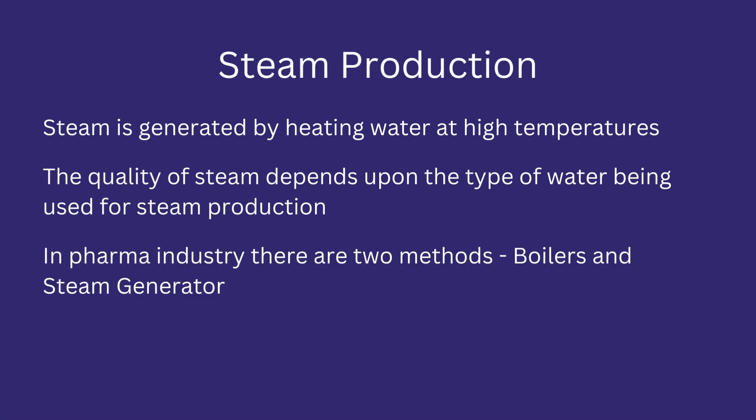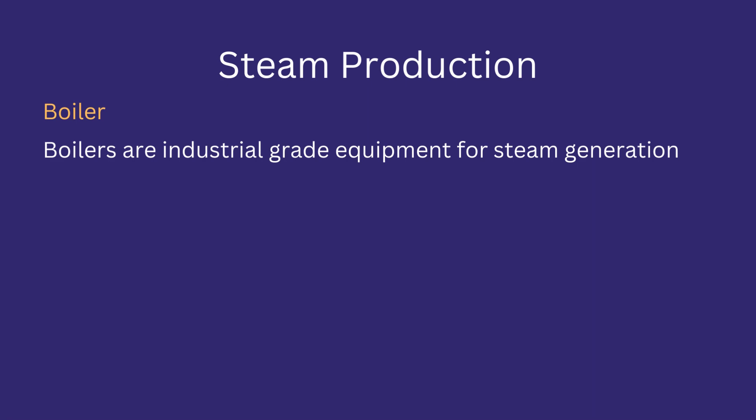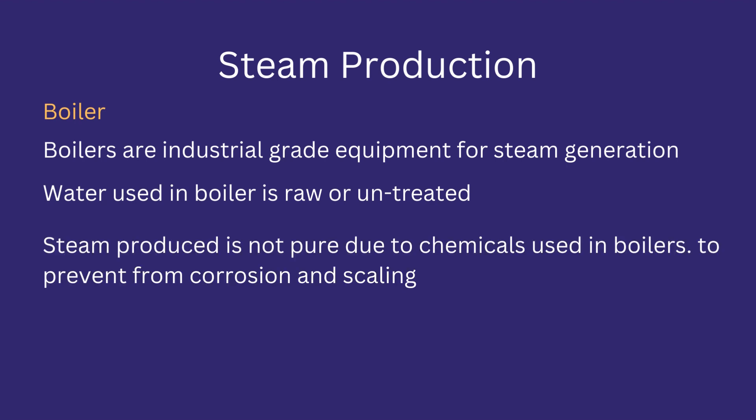In the pharma industry, there are two methods of generating steam: boilers and steam generators. Boilers are industrial-grade equipment used to generate steam, and their internal structure allows for easy heat transfer to convert water into steam. The feed water used in the boiler is untreated or raw and is not pure. In addition to impurities, the feed water also contains chemicals as part of equipment requirements — these chemicals are used to increase the life of internal parts and mechanical structure and to prevent corrosion and scaling.